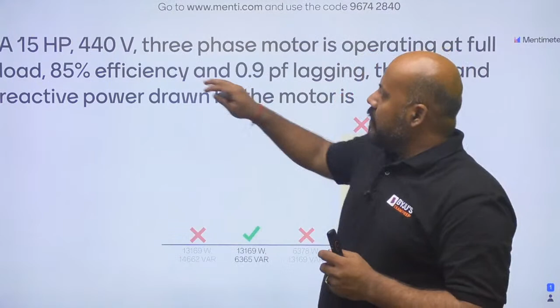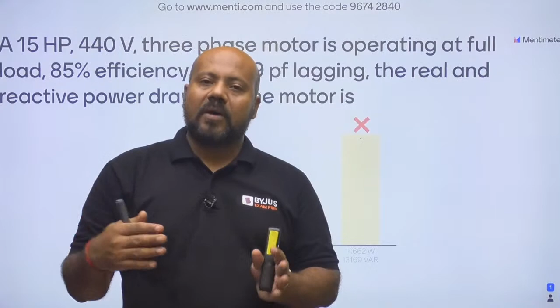He is giving you the rating of the motor in horsepower. Whenever the rating of the motor is given in horsepower, it means he is giving you the output power, because the output of the motor is mechanical. Motor has input electrical power, output is mechanical power. So if he is giving you the horsepower as the rating of the machine, you please understand he is talking about the mechanical output. Output he has given. He is asking you the power taken by the motor. It means what you want? Input power. First you talk about the real power, and from the power factor relation you can find the reactive power also.